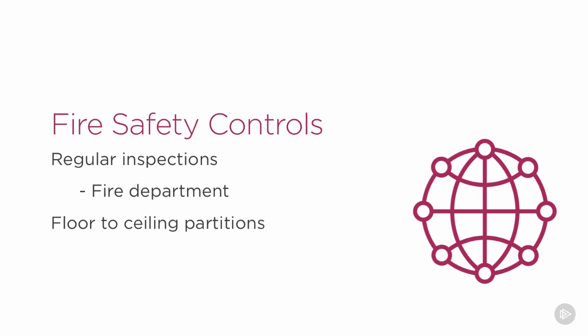Another thing that can stop the spread of fire is walls. We have, for example, the walls around the server room should go directly from the floor right up to the true ceiling. We don't have these fake walls that there's actually a gap above them, above a false ceiling, because that could allow a fire to jump from one room to the next. It also can allow smoke and so on to also pass from one area to another.